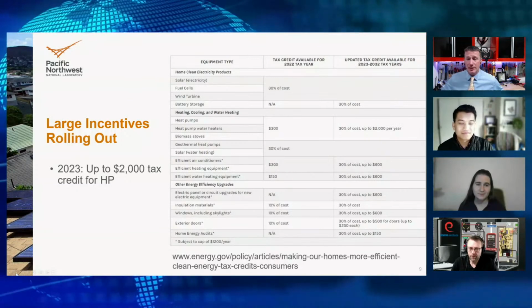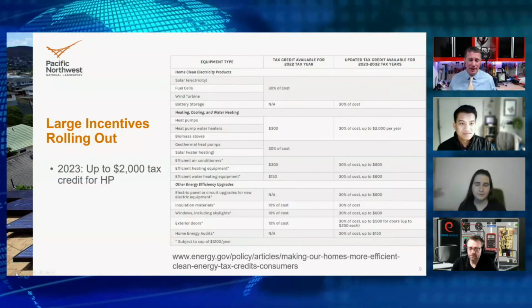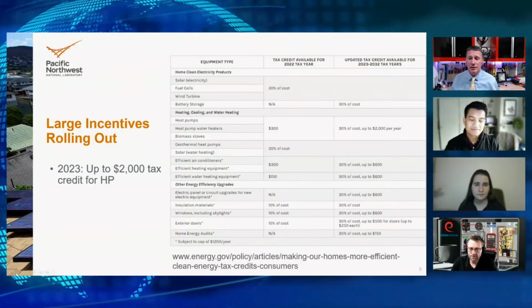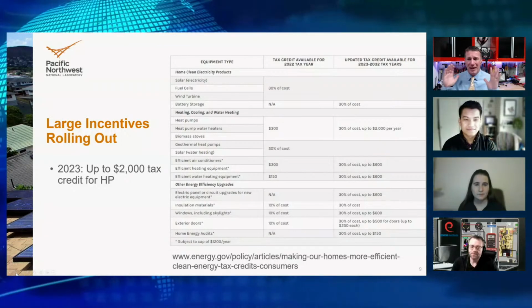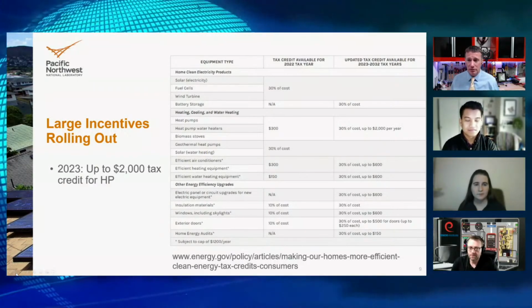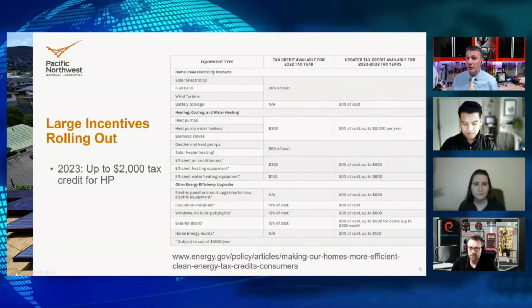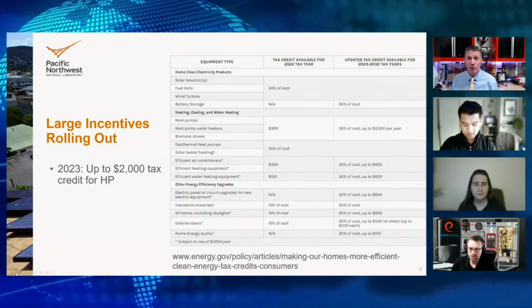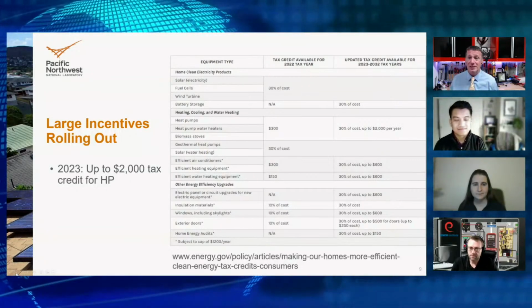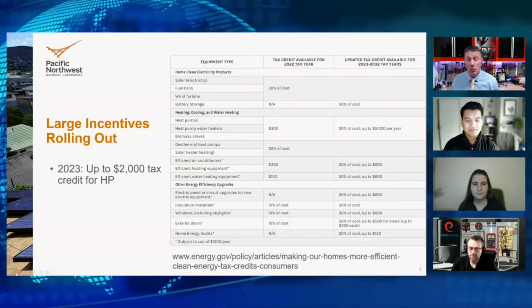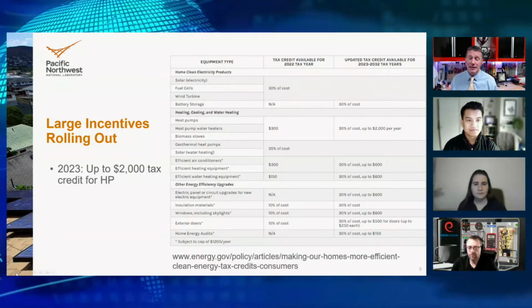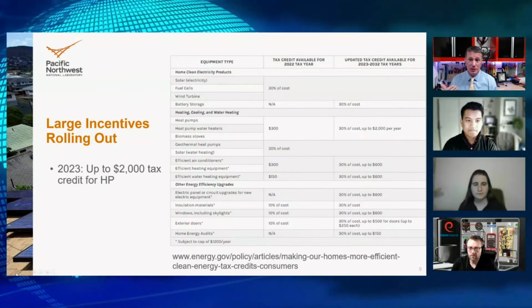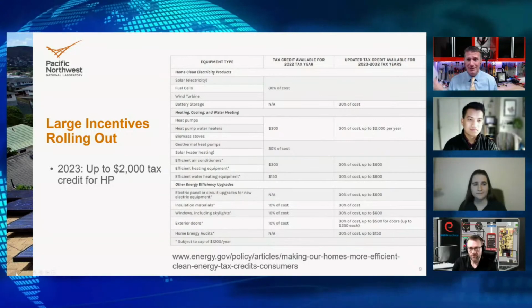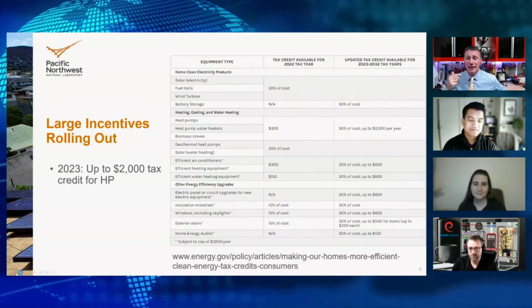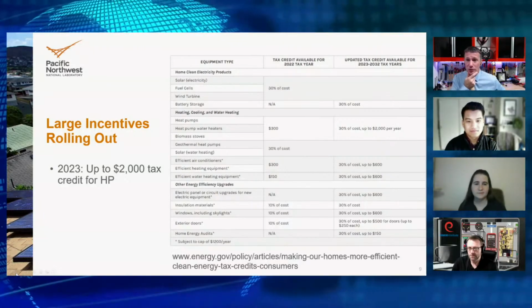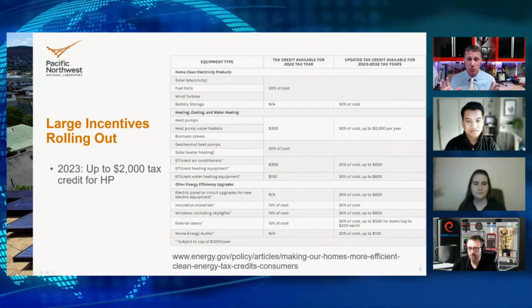That's something a lot of our contractors are going to have to look at going forward. We've had a lot of inefficient systems for decades, and we're starting to understand the importance of doing package analysis, looking at the envelope of a structure to see what improvements we can make. We're seeing a lot more duct and envelope testing, blower door testing, and demand for efficiencies. We now have states and jurisdictions requiring blower door testing on new construction to validate how tight the system is, which gives us the opportunity to potentially reduce the BTU load, the capacity, of the structure. So if we look at that, what are our first steps? Are we just replacing a piece of equipment, or can we look at all the options we have?